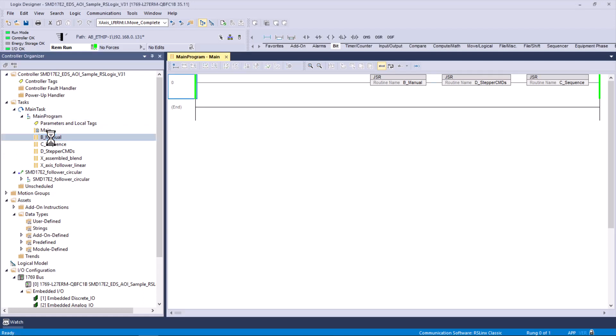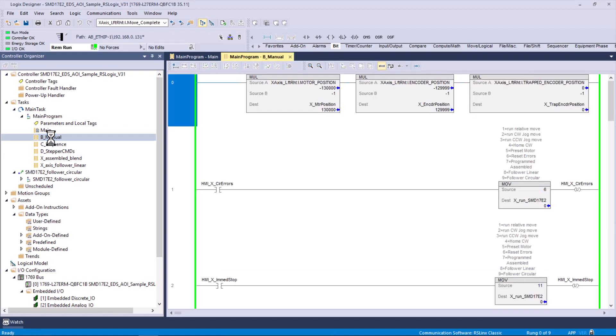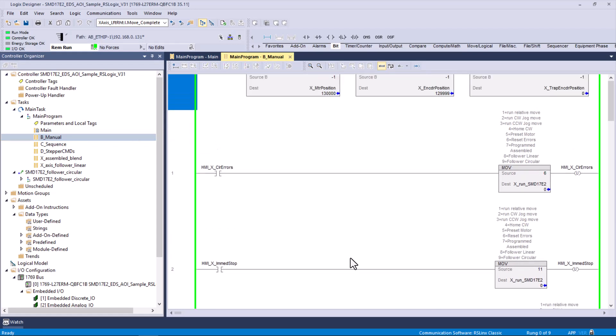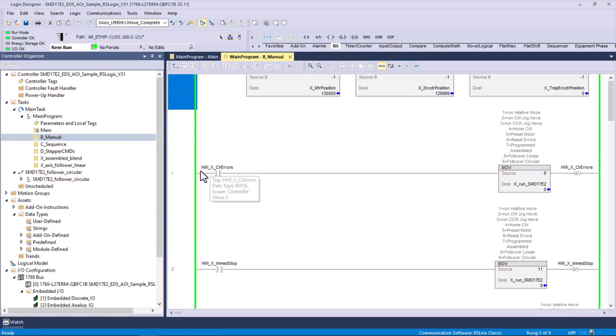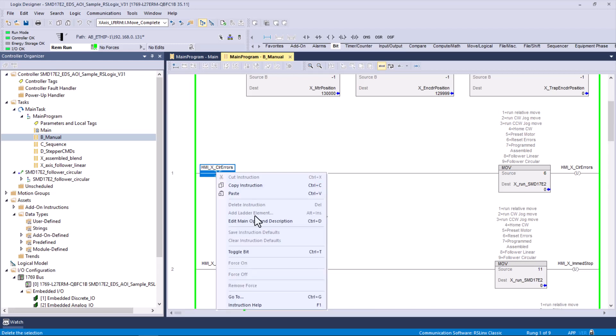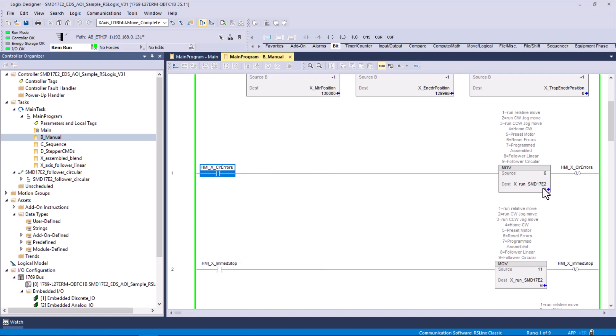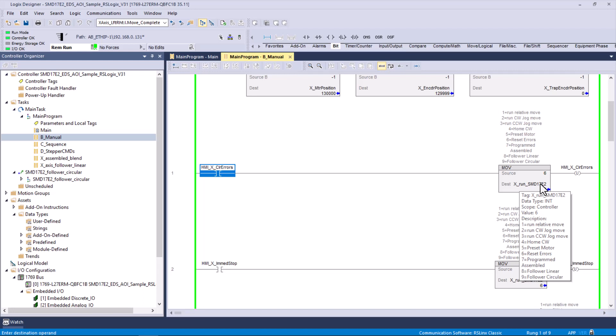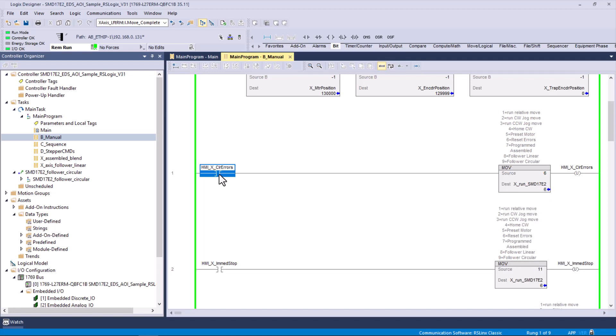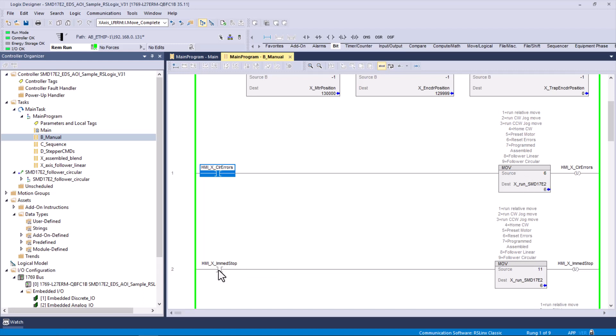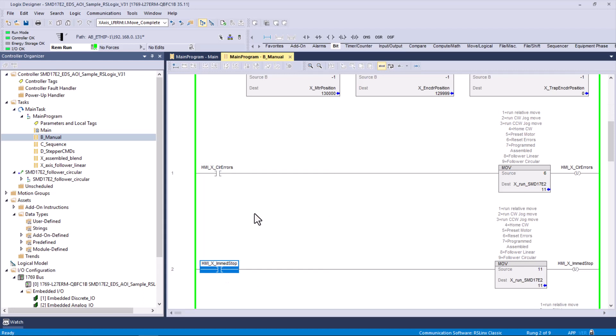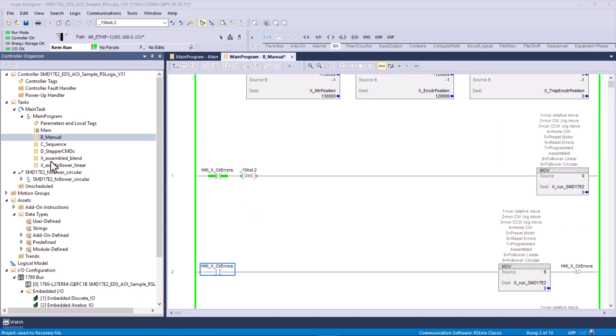In the manual routine, this is logic that I added. I wanted to notice that anytime I'm going to have an operator intervention or an external public interface, I usually put HMI on it and it eventually ends up on an HMI. HMI for the x-axis clear errors. When I toggle this, it puts a 6 into this tag that controls the commands for the stepper device, and then it unlatches itself. You don't have to toggle this on and toggle it off. It clears itself after it puts a 6 in there.